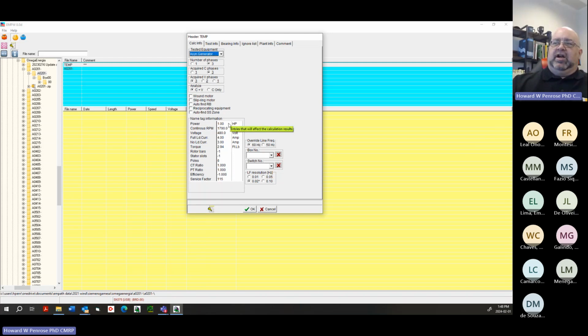But I come in here and then I will put in my kilowatts or horsepower. I can't change this to kilowatts. I've asked them to change that. This is a number you want to be as close to what the actual is as possible. So if it's actually kilowatt, put in the kilowatt value there. And then here, this machine should be 2016 RPM. This will be off the nameplate, 690 volt. Current is 1520.